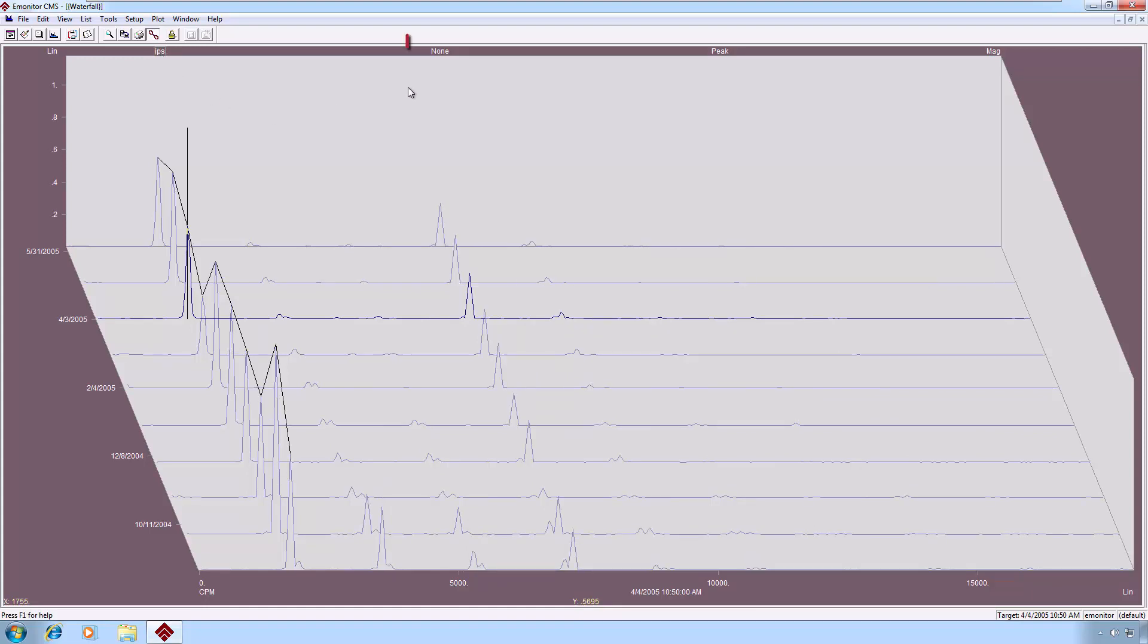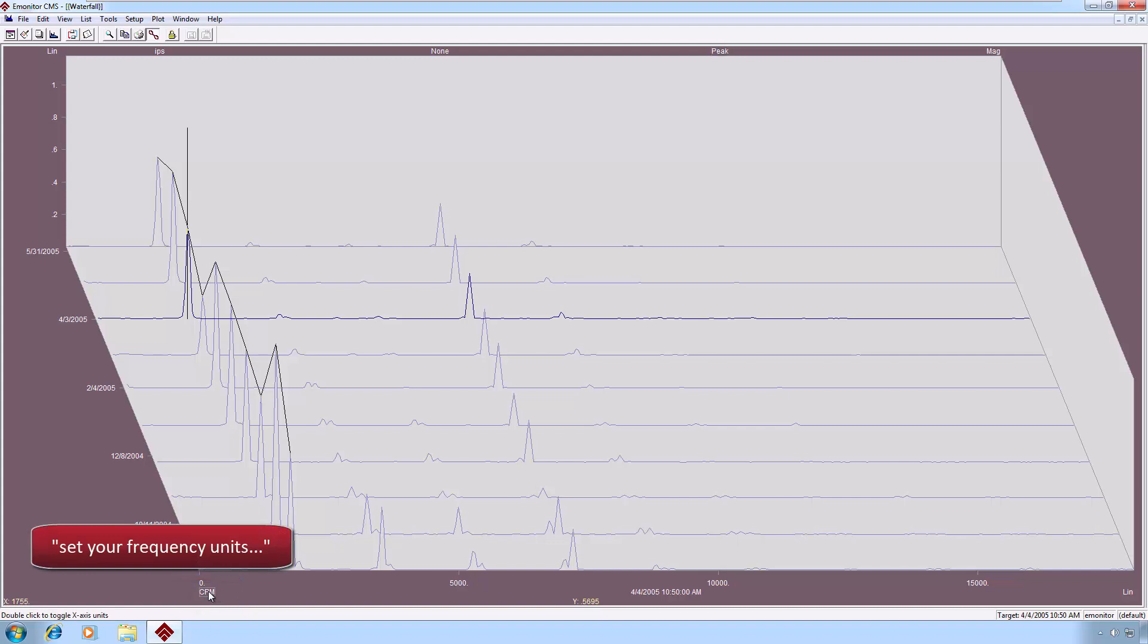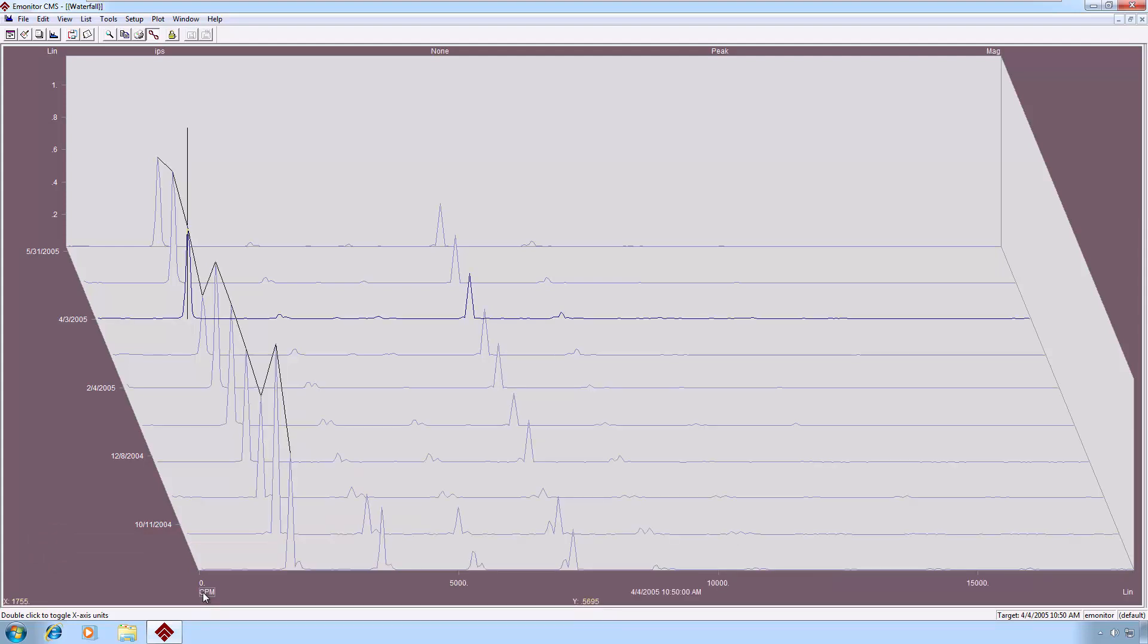We're currently using no filter on this particular measurement, and you can also toggle peak signal detection to peak-to-peak or RMS. And down here, you can track your speed in either CPM, in orders, or in hertz. And then the x-axis scale will change to reflect that. All right, let's move on.